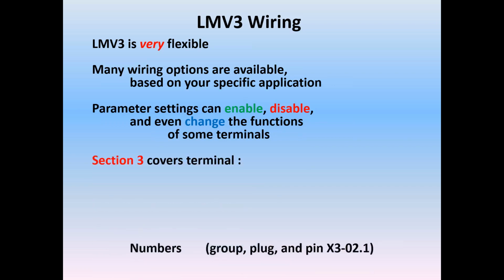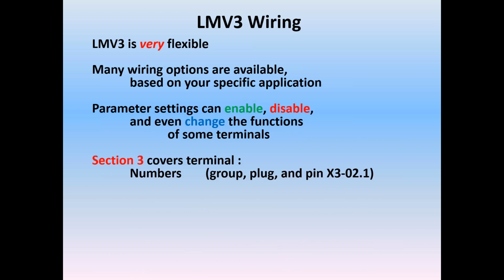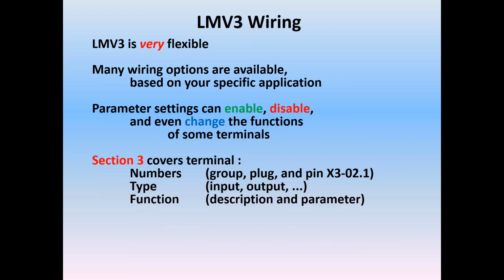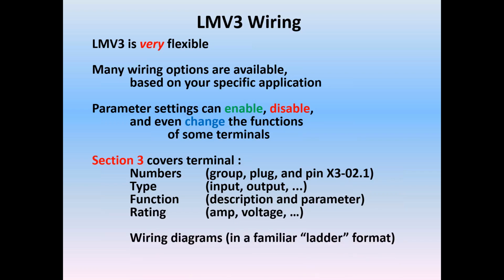Section 3 covers the terminal numbers, which would be the plug group and pin, like 321, which would be air pressure switch. The type, whether it's an input or output, air pressure would be an input. The function, description, and the parameter. So that would be air pressure would be the function, and then the parameter number will be shown. And the rating of that particular terminal, how much voltage and amperage it can be used on it. Plus, we have an additional section on all the wiring diagrams in a familiar ladder format.